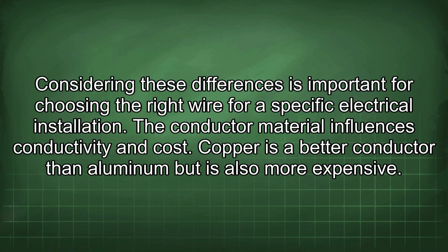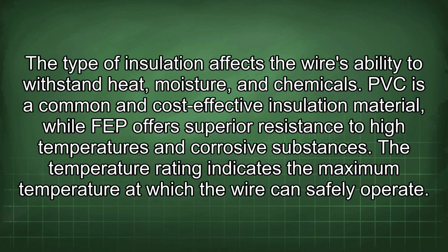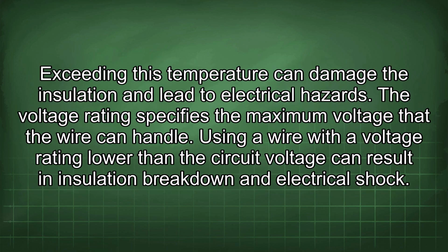The conductor material influences conductivity and cost. Copper is a better conductor than aluminum, but is also more expensive. The type of insulation affects the wire's ability to withstand heat, moisture, and chemicals. PVC is a common and cost-effective insulation material, while FEP offers superior resistance to high temperatures and corrosive substances. The temperature rating indicates the maximum temperature at which the wire can safely operate. Exceeding this temperature can damage the insulation and lead to electrical hazards.